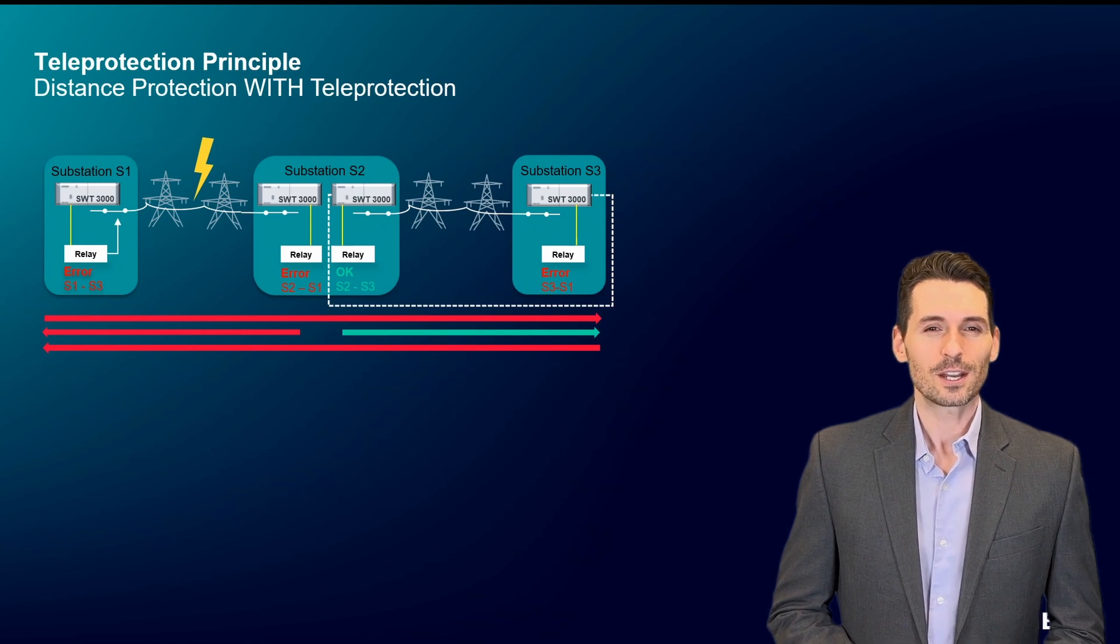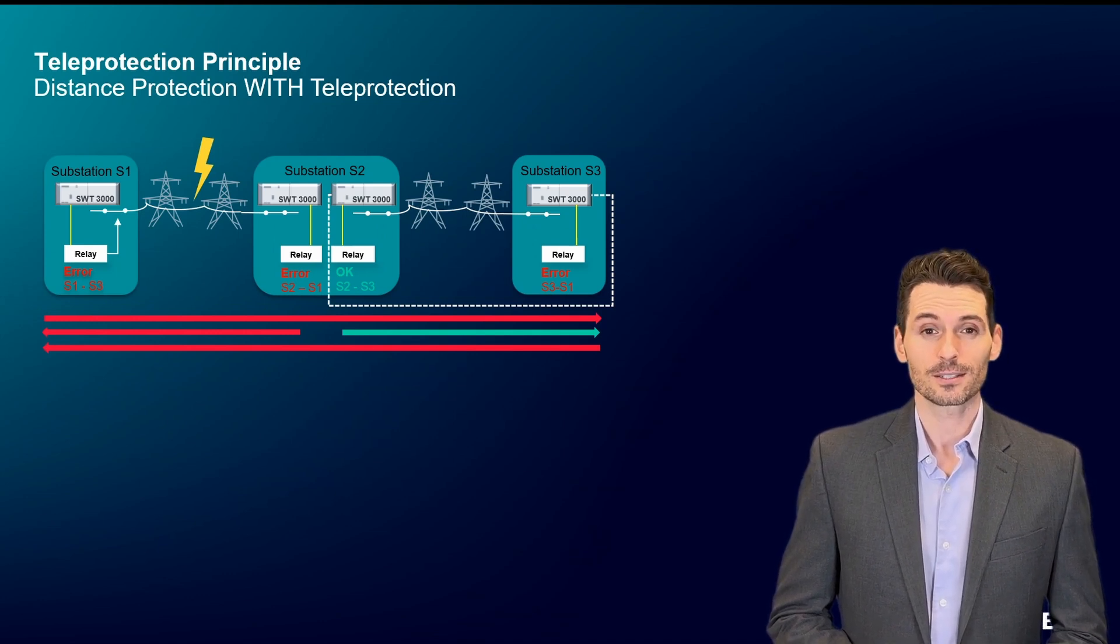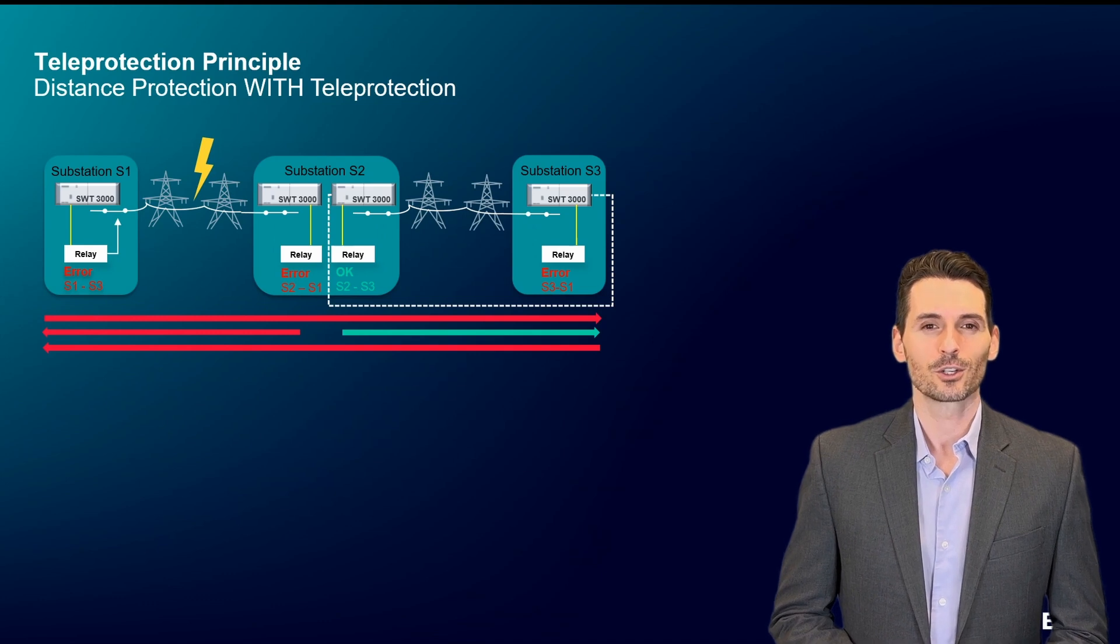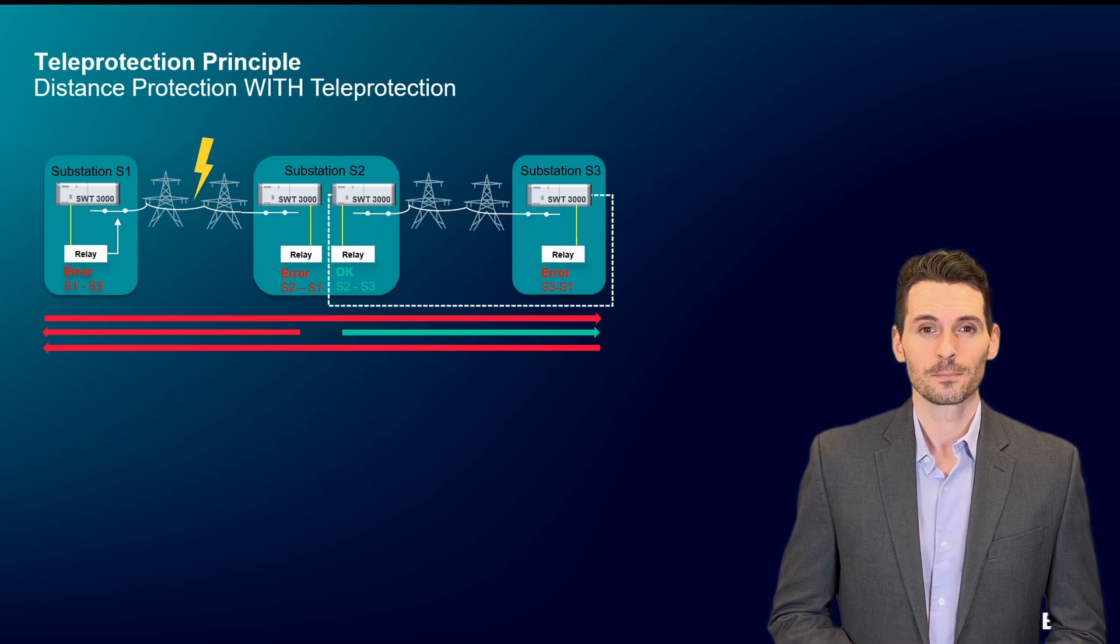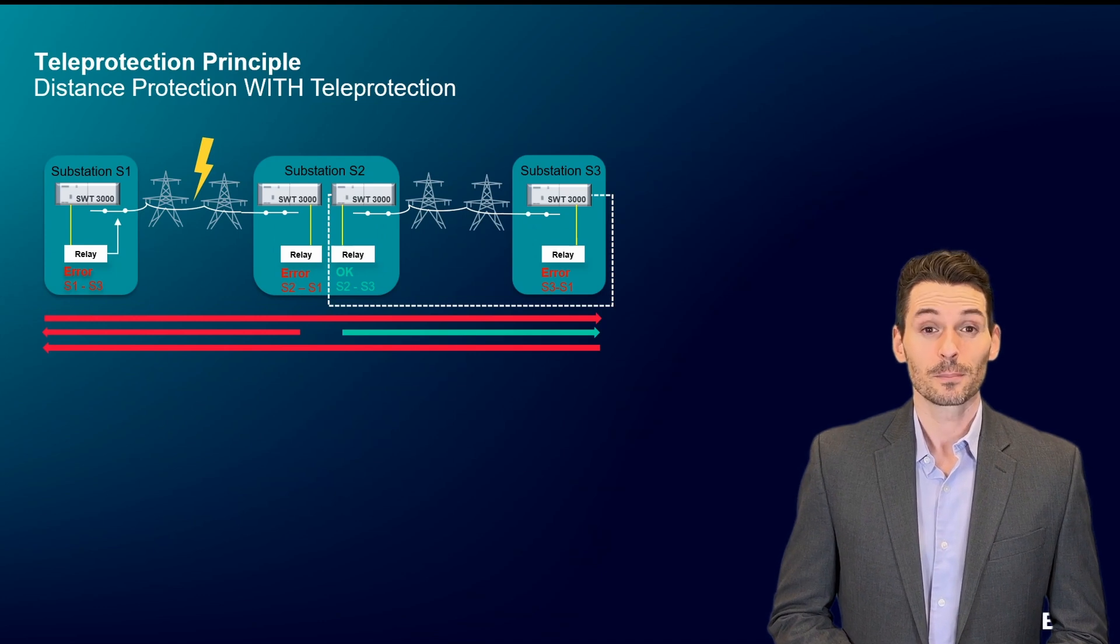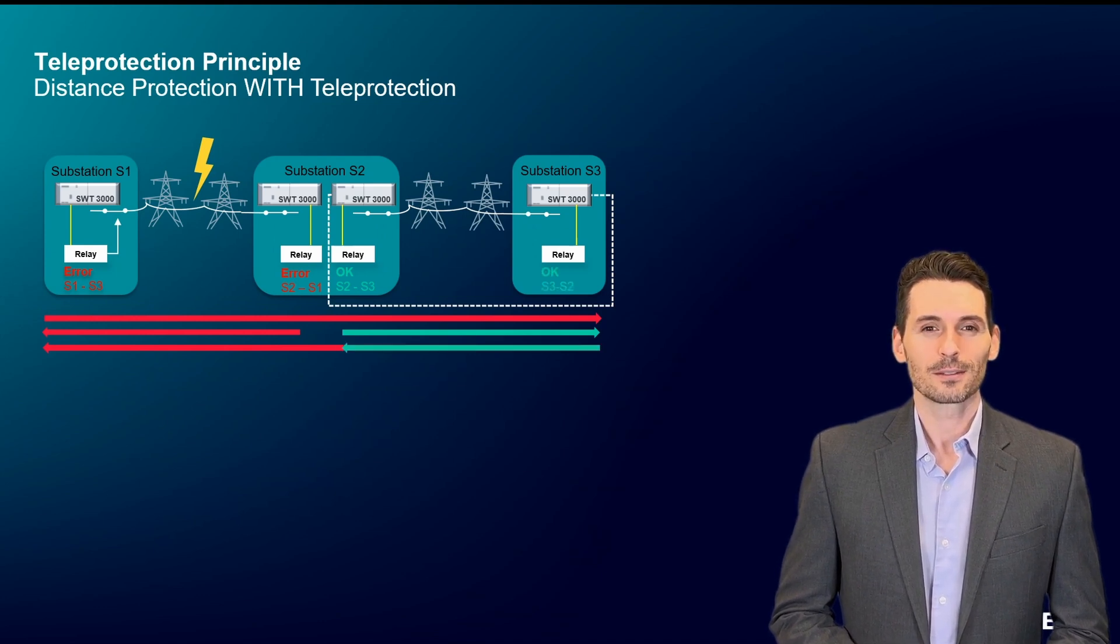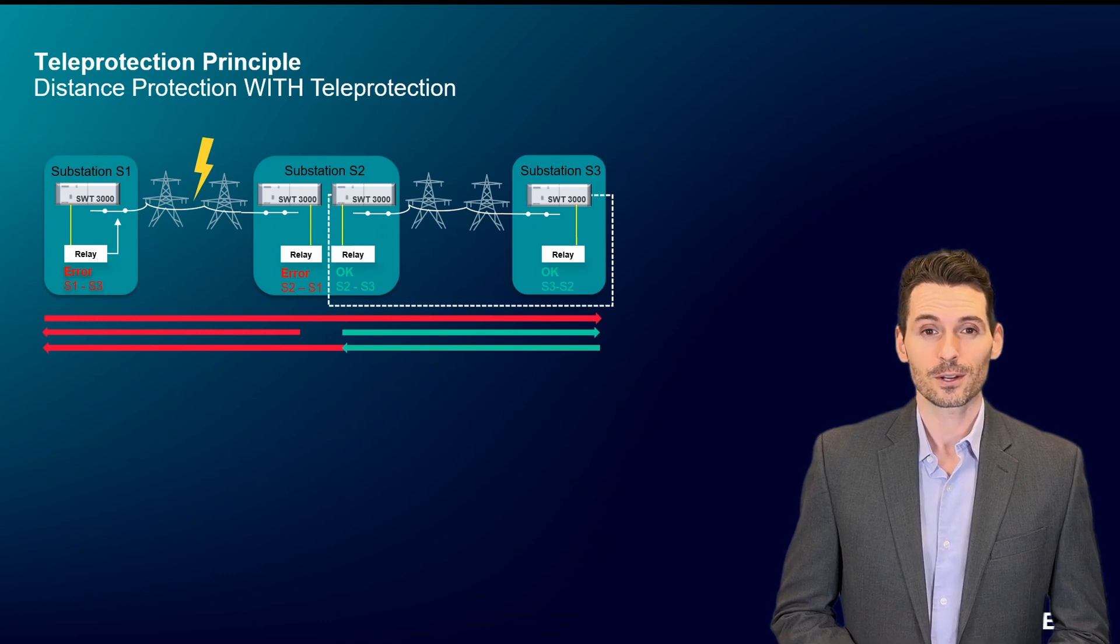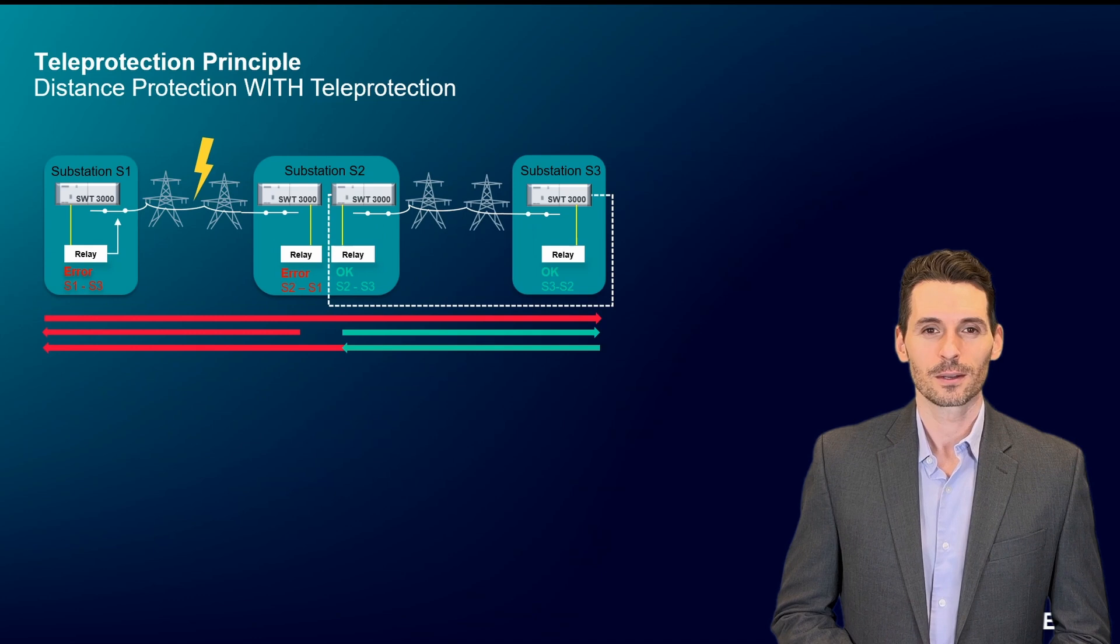This information is also reported to the assigned protection signaling system. The communication between the two substations goes as follows: Substation 2 tells substation 3 that the line is OK. The protection relay in substation 3 accepts the change of status from error to OK and doesn't initiate any switching.